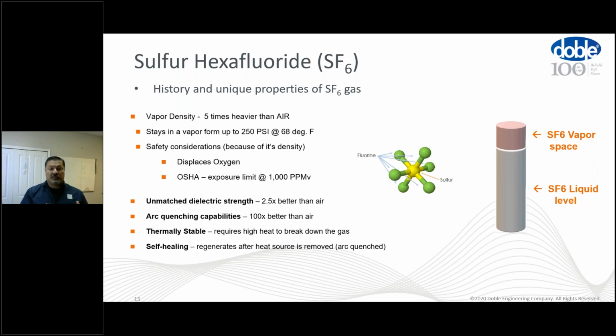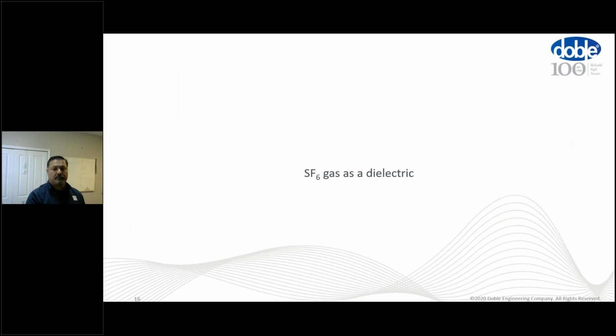Unmatched dielectric strength, which means it's 2.5 times better than air as a dielectric. It's 100 times better than air when it comes to arc quenching. And it requires high heat to break down the gas. So that's what would break it down, if anything: continuous high heat, like a fault, a continuous arc or something to that effect. But when that arc or that high heat is eliminated, it regenerates and is ready to go and do its job all over again.